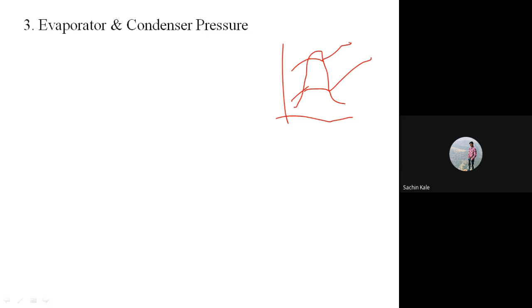While selecting any refrigerant depending upon evaporating and condenser pressure, we have to select the refrigerant which will have both values of evaporator and condenser pressure as positive. Why is it required? Suppose your evaporating pressure is below atmospheric pressure, that means vacuum pressure, and condenser pressure is a positive gauge pressure. If you operate the evaporator at a vacuum pressure and there is leakage inside the pipe of that evaporator, then what will happen? Instead of the refrigerant leaking out, the system will suck the air from the atmosphere, and there will be a mixture of air and refrigerant. That will not be a desirable case.